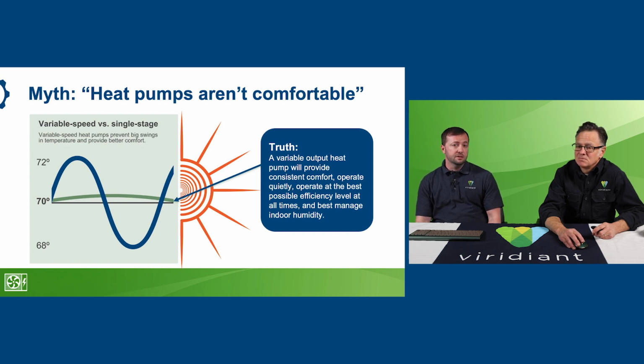This is the best comfort, and it's also a quieter system because of this. Additionally, it increases the system life. It's all those starts and stops that are really hard on HVAC equipment. So by having the system run more continually and longer, you reduce that number of starts and stops, and therefore the wear and tear in the HVAC equipment.